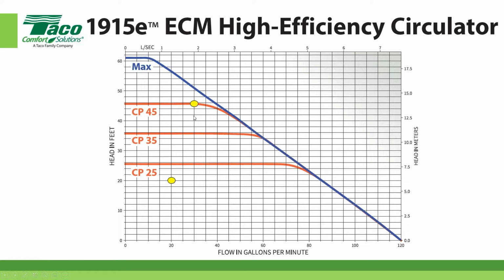Okay. And you can use that same calculation backwards. Again, the same calculation with half the flow would tell me where the new head would be. Look, it's down here at around 5, less than 5 foot of head. So 2, 4, 6, 8, 10. No, right at 5. 2, 4, right at 5. 5 foot of head if I drop it back to 10 gallons a minute. So that's why you see these things that look like that.